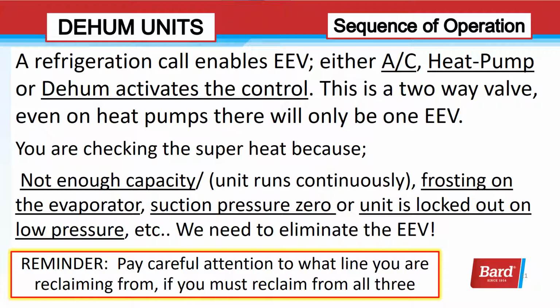And you're checking the superheat for some reason. Not enough capacity and the unit runs continuously, or you have frosting on the evaporator. Maybe your suction pressure is at 0, or the unit is locked out on low pressure. We need to eliminate the EEV as the cause. And remember, pay careful attention to what line you're reclaiming from if you must reclaim from all 3 lines.